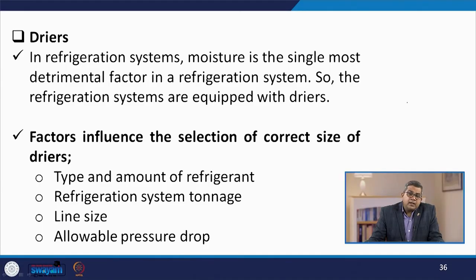The dryer is the next auxiliary device. In a refrigeration system, moisture is the single most detrimental factor. Refrigeration systems are therefore equipped with dryers. Various factors influence the selection of the correct size of dryer: the type and amount of refrigerant — dealing with both quantity and quality — the refrigeration system tonnage, and the line size and allowable pressure drop.